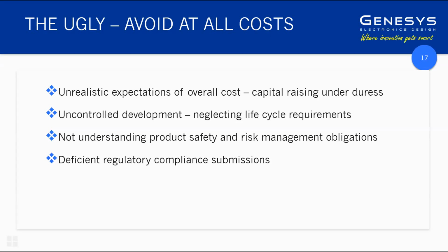Yeah, well, product safety we touched upon with IEC 60601-1 and risk management ISO 14971. These are mandated standards that are called up as being applicable to medical products. And in particular, risk management should be done for any product development, but normally not done in a formal manner. There is an obligation to do risk management in a formal manner and within the context of risk being risk of harm to patients, users, or the environment.